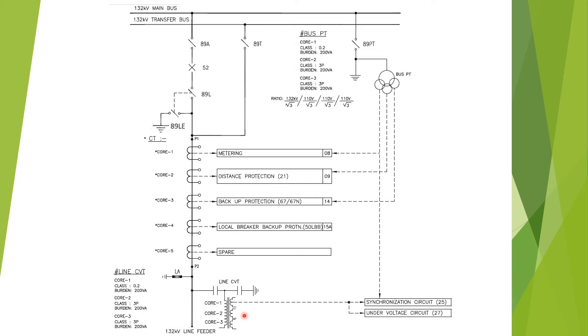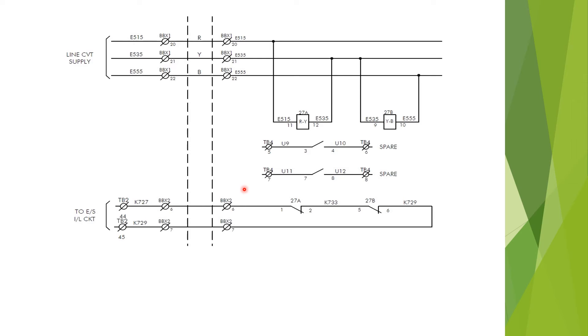How the under-voltage relay contact is used for the line earthing switch interlock will be discussed now. For each phase there exists one CVT. The secondary input from the CVT is taken to the CRP panel to supply the two terminals of the under-voltage relay. Since there exist three CVTs, two under-voltage relays are used for the line earthing switch interlock — 27A and 27B. The first under-voltage relay 27A is used between the red and yellow phase CVT secondaries; 27B uses the secondary voltage between the yellow and blue phase.